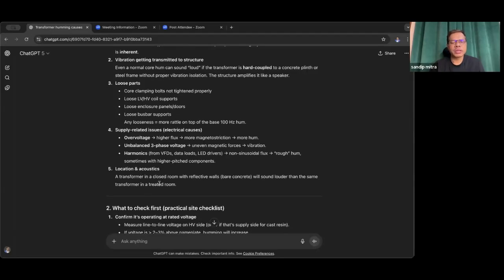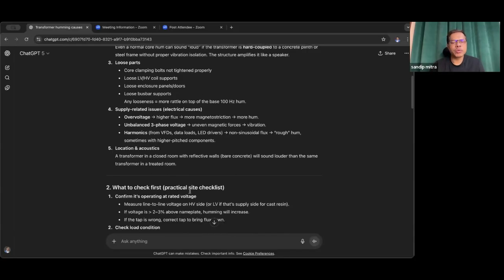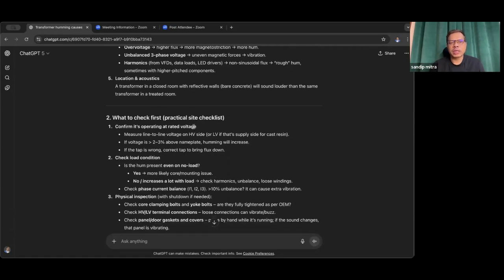Locations and acoustics: a transformer in a closed room with reflective walls, bare concrete, will sound louder than the same transformer in a treated room. Now, what to check first? There is a practical checklist at the site level. Confirm it is operating at rated voltage. So measure line-to-line voltage on the HV side, or on the LV side if that is the supply side for cast resin. If voltage is greater than 2 to 3% above nameplate, humming will increase. If the tap is wrong, correct the tap to bring flux down.